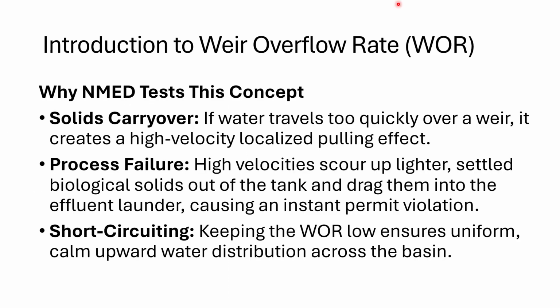So why does NMED want the operators to know about this concept? Well, the idea is if we're pushing water over that weir at too fast a rate, it's going to create kind of a pulling effect, and there's a potential for solids to carry over from that primary or secondary clarifier into the effluent launder and onto the next stage, and that we don't want.